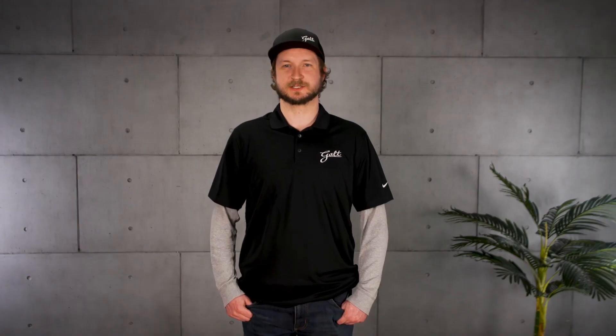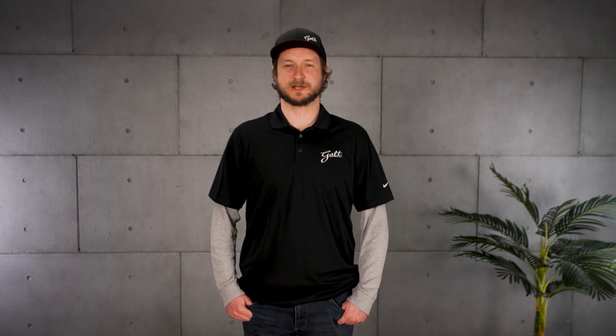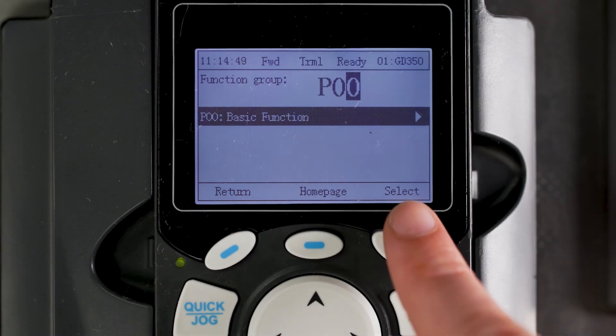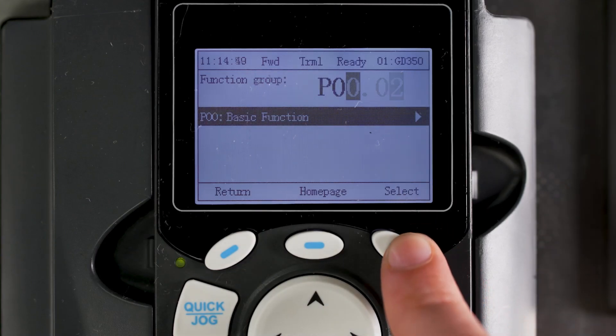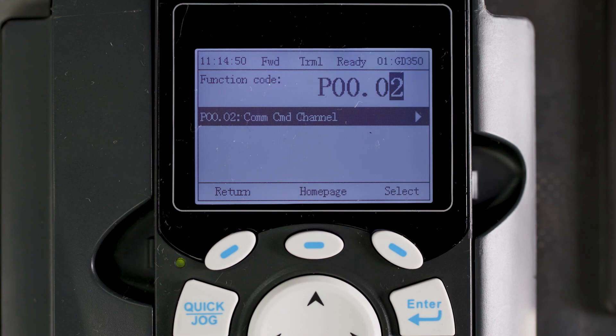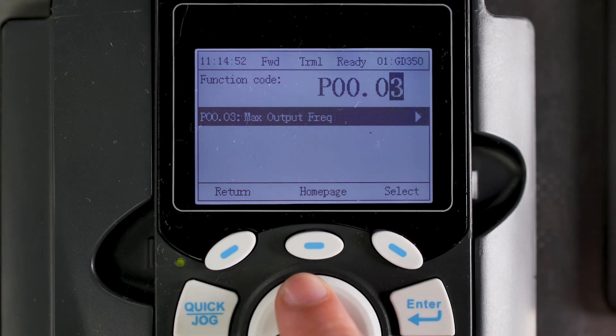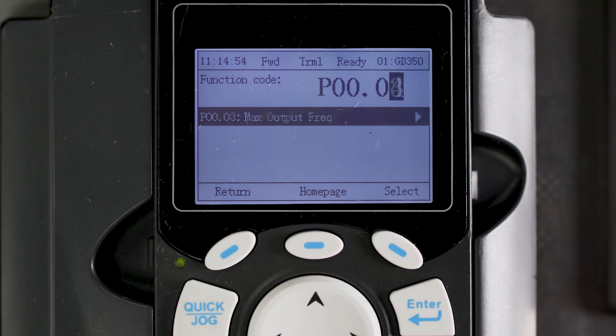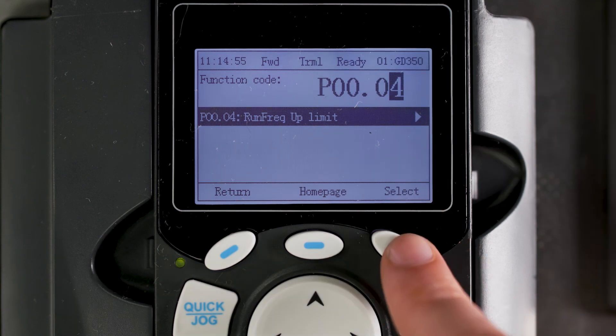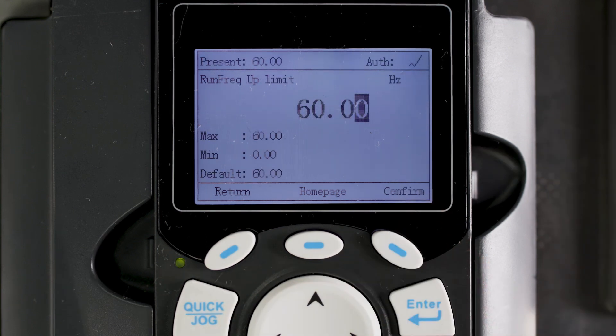Now that you understand how to find and adjust parameters in the G500 drive, we'll discuss commonly used parameters. You can review Chapter 6 of the G500 manual for the entire list of parameters. We'll continue with the first P00 group parameters for the basic functions. Parameters .03 and .04 will both adjust the maximum output frequency, which is set to 60 Hz by default.